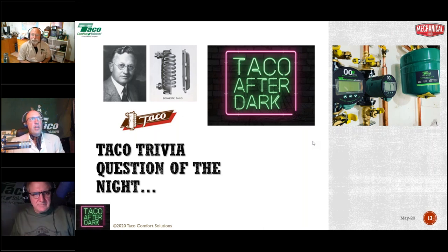Well, there was a good question that came in a little while ago. John Allen was asking, is there any savings running a 30 to 35 degree delta through a baseboard application where we're typically designed for a 20 degree delta, especially with a ModCon boiler? And Rick had answered saying, yes, the average temperature rules, it does work and it does work well. The only thing you need to watch out for, if you set it up for, say, a 35 degree delta, is the last piece of baseboard on that loop, which would see a cooler temperature. So just make sure you have enough length of baseboard in there to handle that lower temperature those end radiators are going to see.